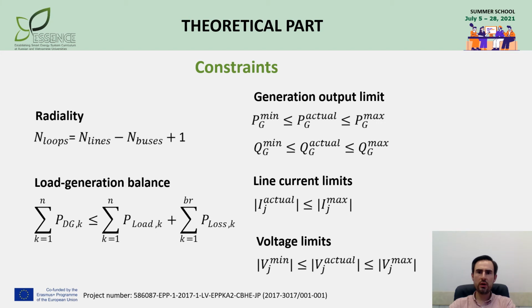Among most used constraints for network reconfiguration tasks are the following. Since we consider a distribution network whose topology is usually kept radial in order to simplify protection schemes, the radiality shall be checked during optimization. If any loop is identified according to the condition on the slide, this case is excluded from analysis. The rest of constraints are quite usual for all power flow tasks: load generation balance, generation limits, line current limits, and nodal voltage limits.